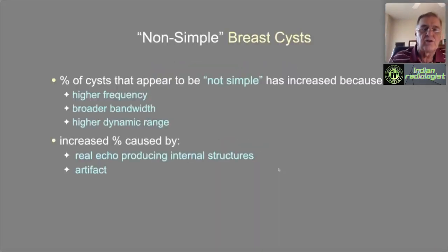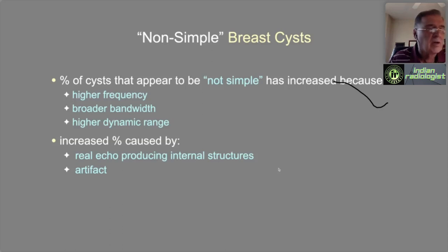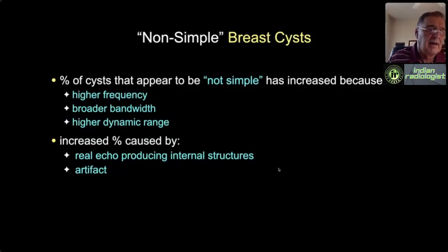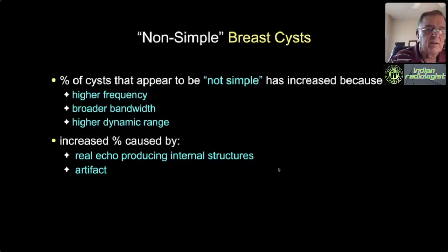I have no disclosures. The percentage of non-simple cysts is higher today than 20 or 30 years ago. This is because we've pushed scan parameters—frequency so high, bandwidth so wide, and dynamic range so wide—that we're creating haze inside the cyst. But secondly, with higher frequency we have better resolution and we're seeing real proteinaceous and/or fatty debris inside the cyst that creates echoes.